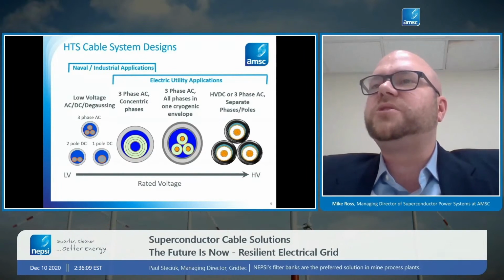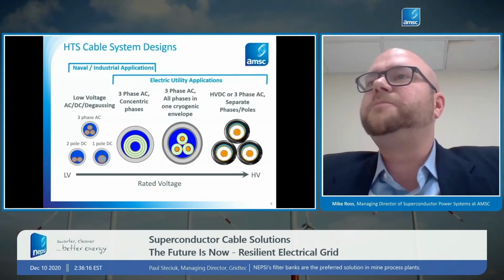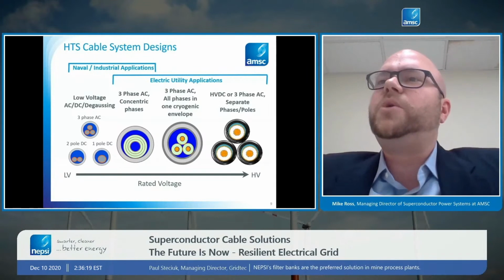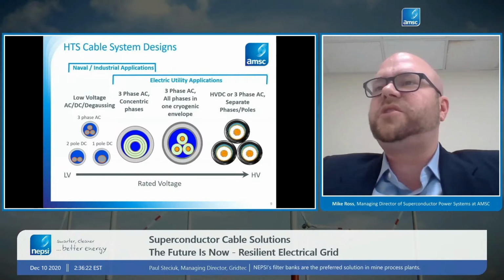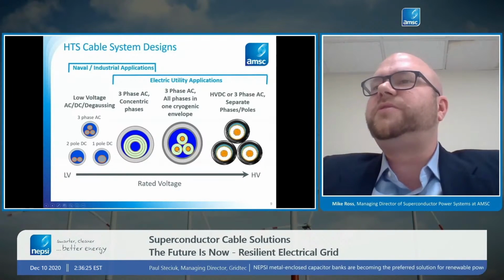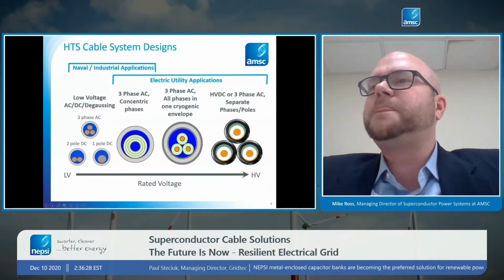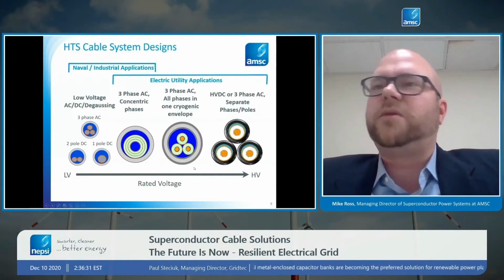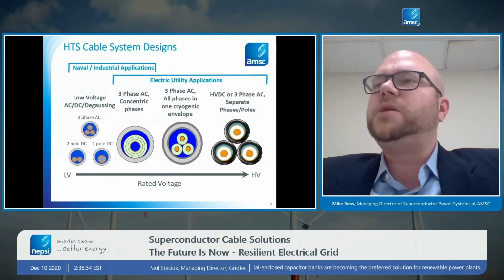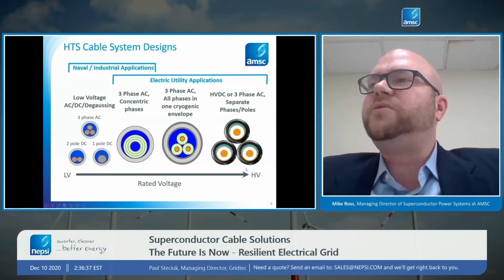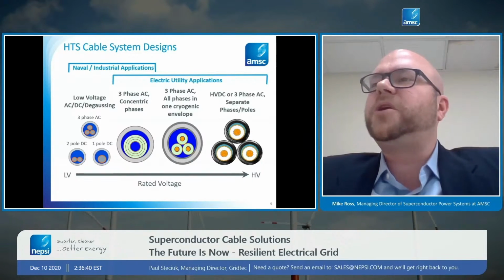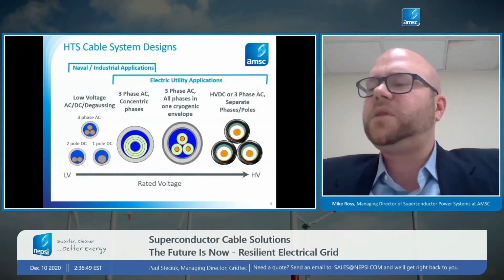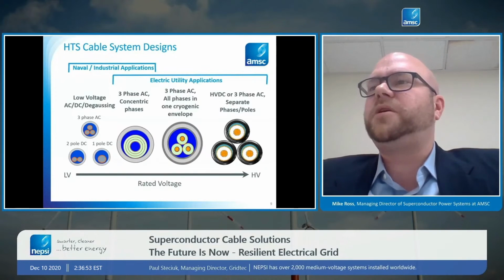And that's because the electrical insulation from phase to phase gets too thick at some point, and you can't meet your bending radiuses anymore. So once we get to 69 kV, we move to what we call 3-in-1, which is this center design. So you have three single-phase cables in a single cryostat. So that's good for 69 kV and some 115 kV applications. But then when we get to transmission cables, 115 kV and above, we go to separate cables in separate cryostats. So you have single phase cables as you would, looks a little bit more like a conventional design. And I'll show some real life applications of all of these designs.